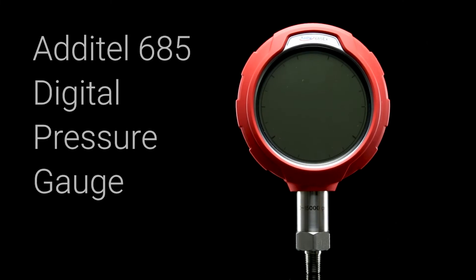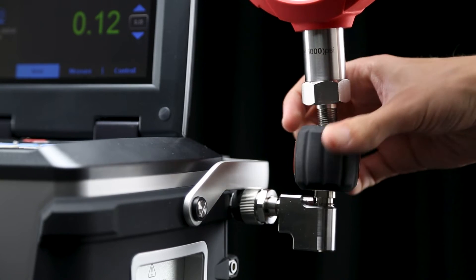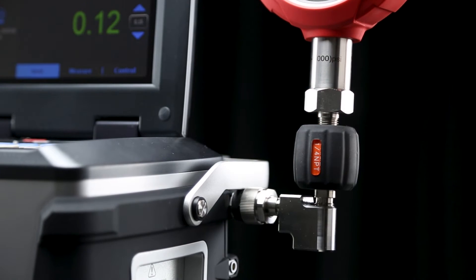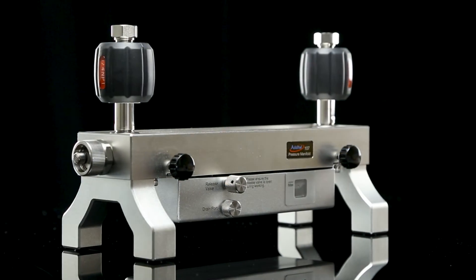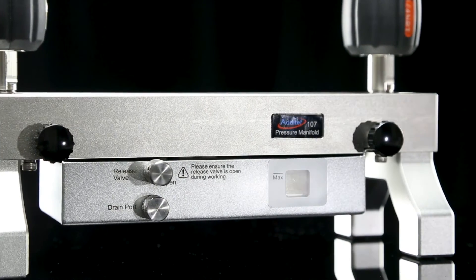In this demonstration, we'll calibrate an Additel 685 digital pressure gauge, which will be attached directly to the 762 by hand tightening the quick connect fitting on the right hand side of the device. If you want to calibrate multiple devices at a time, you must use the Additel 107 manifold that communicates with the 762 directly to prevent oil contamination.